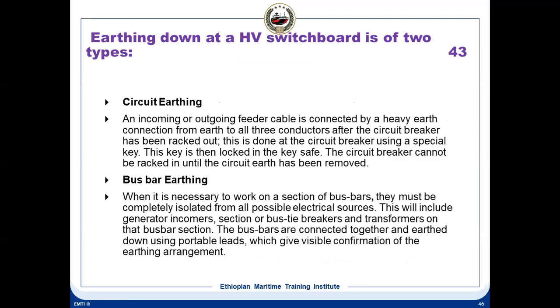There are two types of earthing down, called circuit earthing and busbar earthing. You can do it in two ways. One is circuit earthing and the other is busbar earthing. An incoming or an outgoing feeder cable is connected by heavy earth connection from the earth to all three conductors after the circuit breaker has been racked out. That means you take out the circuit breaker, then you use these earthing cables, connect the cable to the ground. This is done at the circuit breaker using a special key. The key is then locked in a key safe.